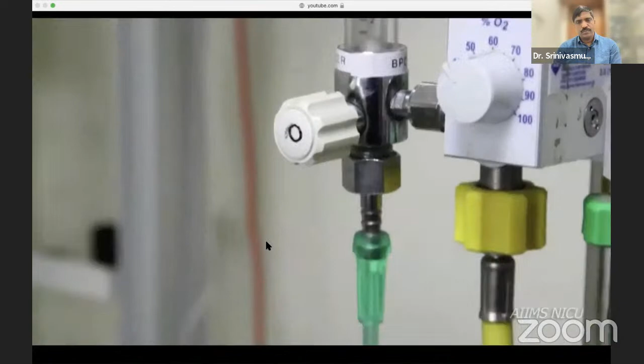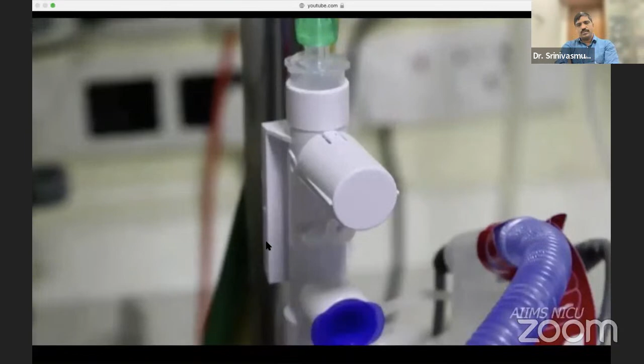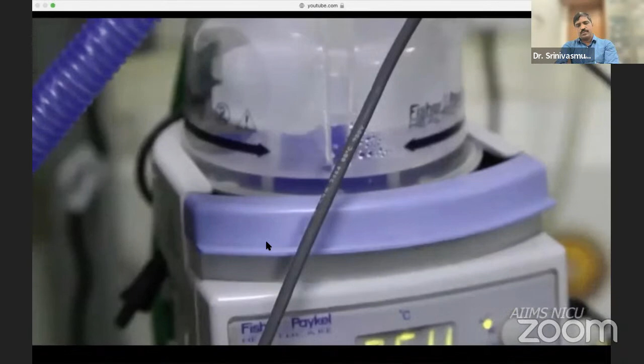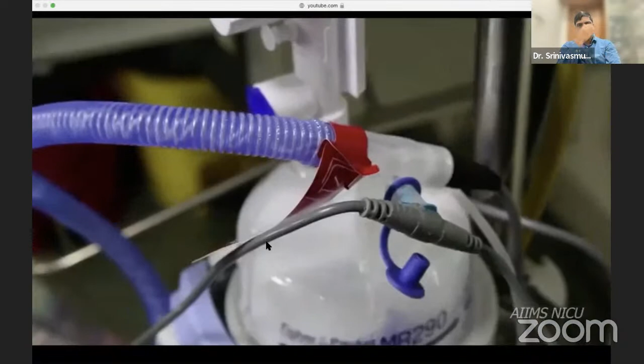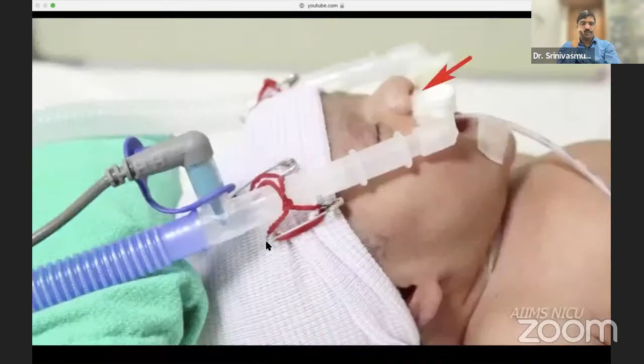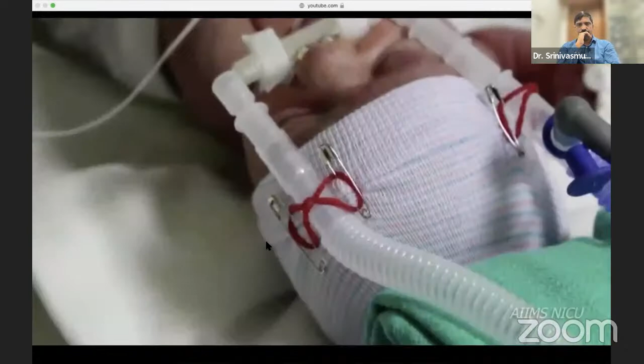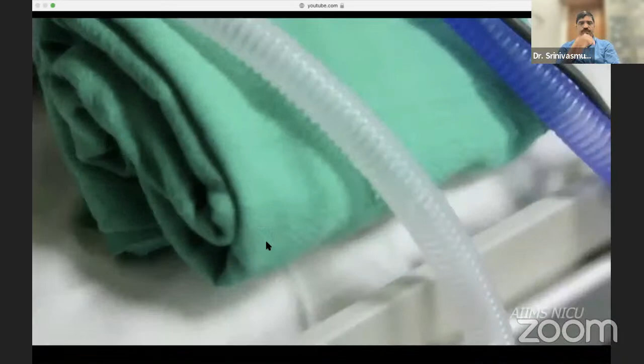Now watch through the gas flow for any leaks in the circuit. Set flow and FiO2. Add water in the humidifier chamber, set the temperature on the humidifier, and connect the heater wire and heater wire probes. Ensure that there is some distance between the prong and columella. Insert the expiratory limb into the bubble chamber. Watch for the bubbling and water level, and also check the set pressure in the bubble chamber.